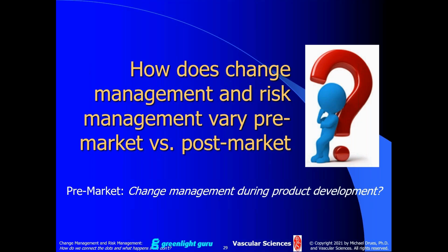Yes, they ask about it from time to time, but when you think about it, it's really none of FDA's business about the changes that we've made prior to our actual final design freeze device that we're going to bring onto the market. In other words, what difference does it make to the FDA if I have 10 different catheters that have a slightly different durometer of material or a slightly different length or diameter or something like that? What is ultimately important to the FDA is the final device, the device that I'm actually bringing to the market that I'm going to sell and so on.